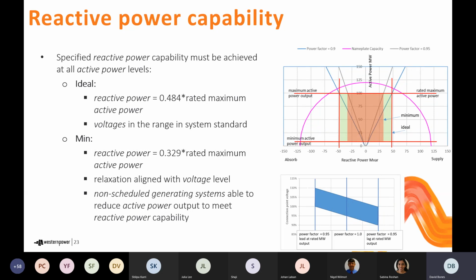Equally well, if you've got low voltage on the network, under those conditions you want to be able to maximise the reactive power production capability. And so the trade-off between those points is indicated by the blue trapezium on the bottom diagram. It allows that relaxation to be specified as part of the generating performance standard. And the last thing that the minimum standard allows is for non-scheduled generating systems to reduce their active power output to achieve the required reactive power capability. It's, if you like, stepping down that capability curve to improve the ability to meet the stated reactive power requirement.